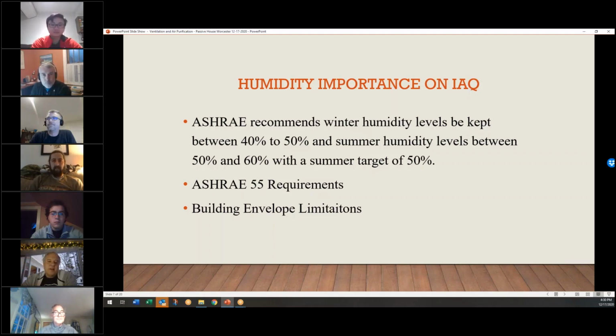And I think ASHRAE 55 doesn't really mandate humidity control, except on the high end. They do want you to control your high end humidity, but it's not a requirement to humidify buildings. They don't require that. And I think up until this point, it's been a very good recommendation not to humidify, because there's a lot of problems that can come from humidifiers if they're not properly maintained, if they run wild. Yeah, I know the Auburn Town Hall went through a major upgrade. It was their humidifiers. They went wild. They got mold spores throughout the building. They had to abate the whole building, and it was closed for like months to do it. And it was all because of the humidifiers.